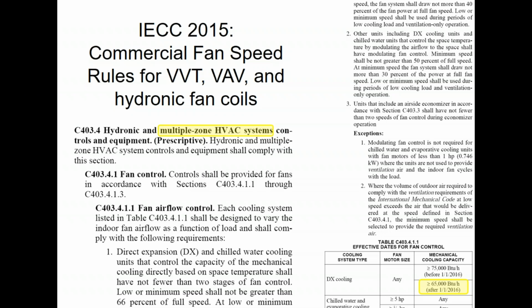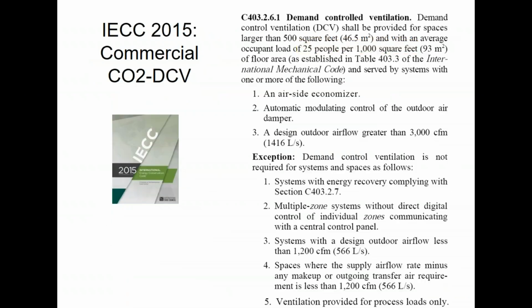However, if you choose to do your fan control with a full variable speed fan instead of a 2-speed fan, then you would be eliminating the bypass damper, because the bypass damper and the variable speed fan would both be controlled based on duct static pressure, and hence they would fight each other. So if you have a full variable speed fan, it'd be more like a VAV type system and you would not have the bypass. If you have a 2-stage fan, it'd be more like a VVT type system and you would still have the bypass. It would just do less work on low load moments.